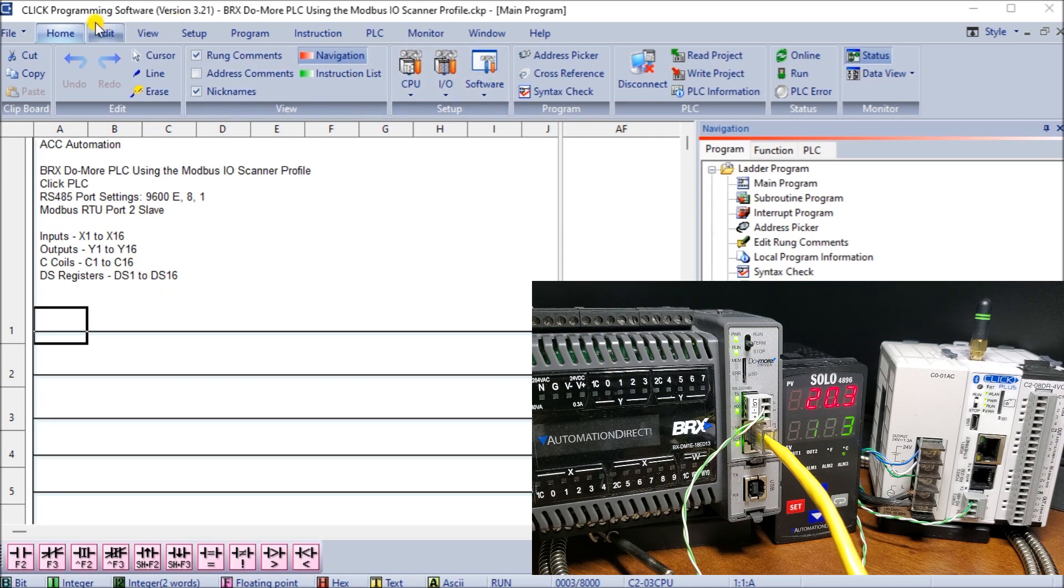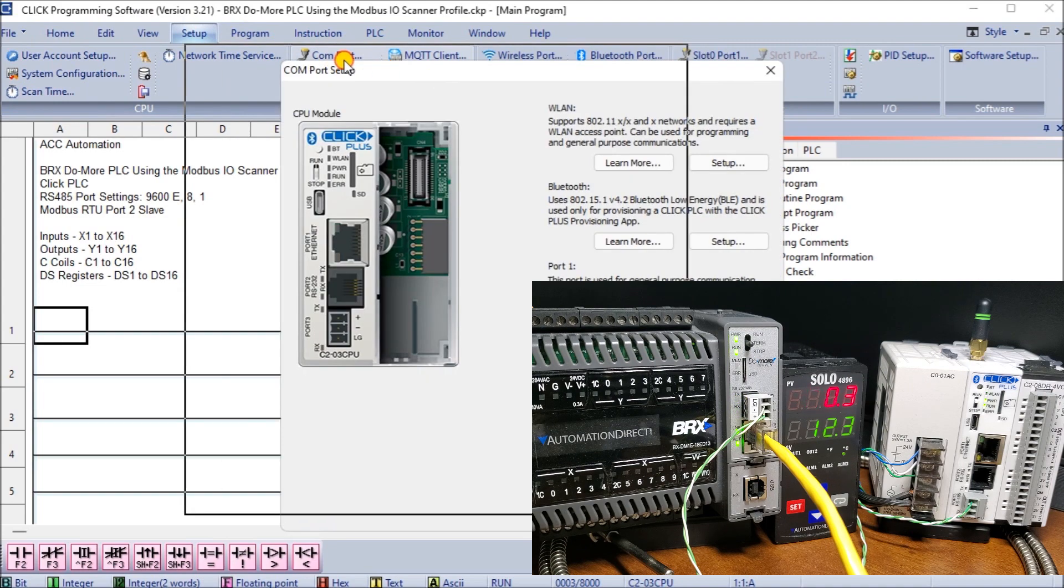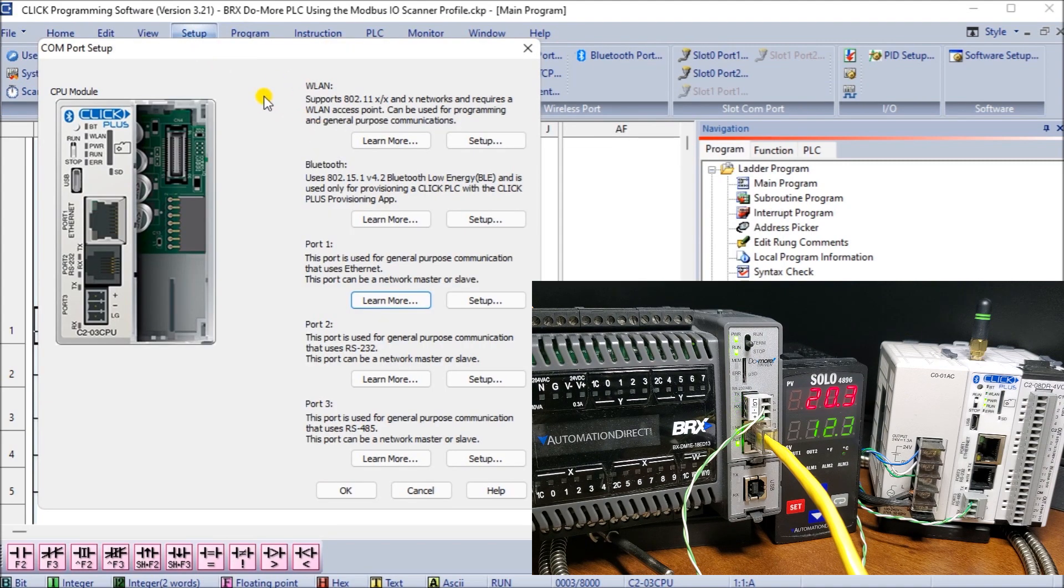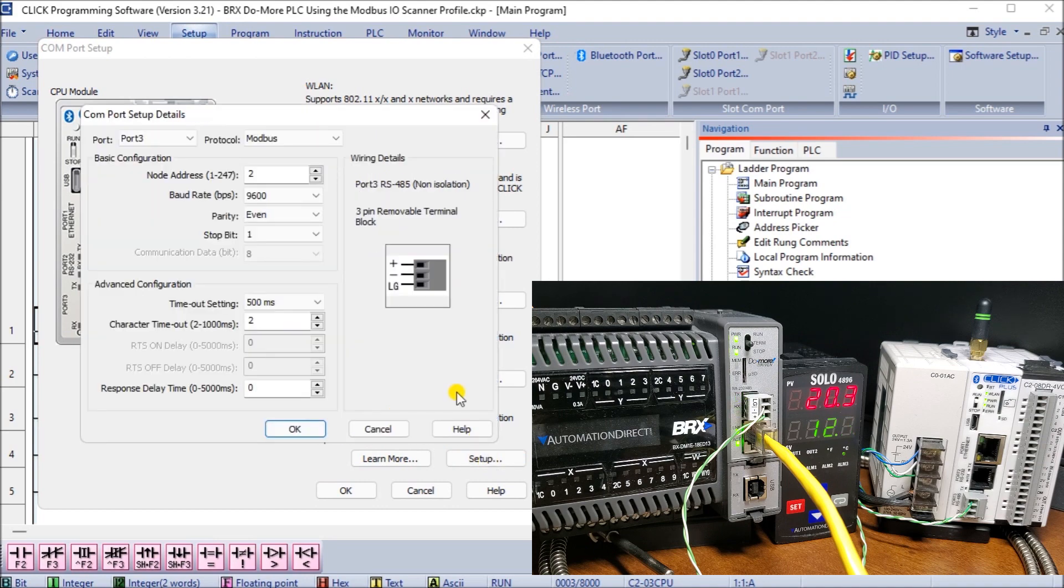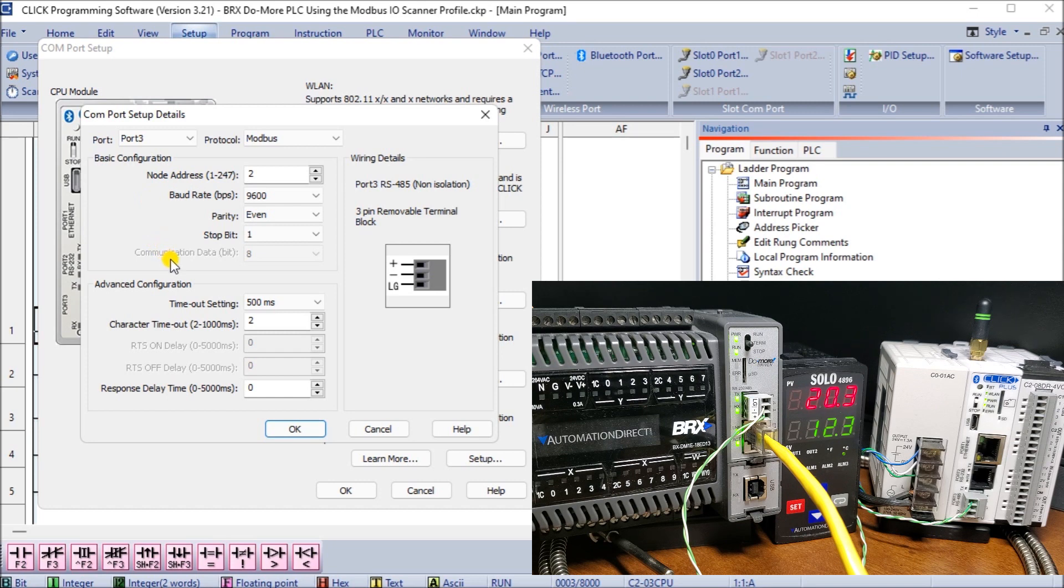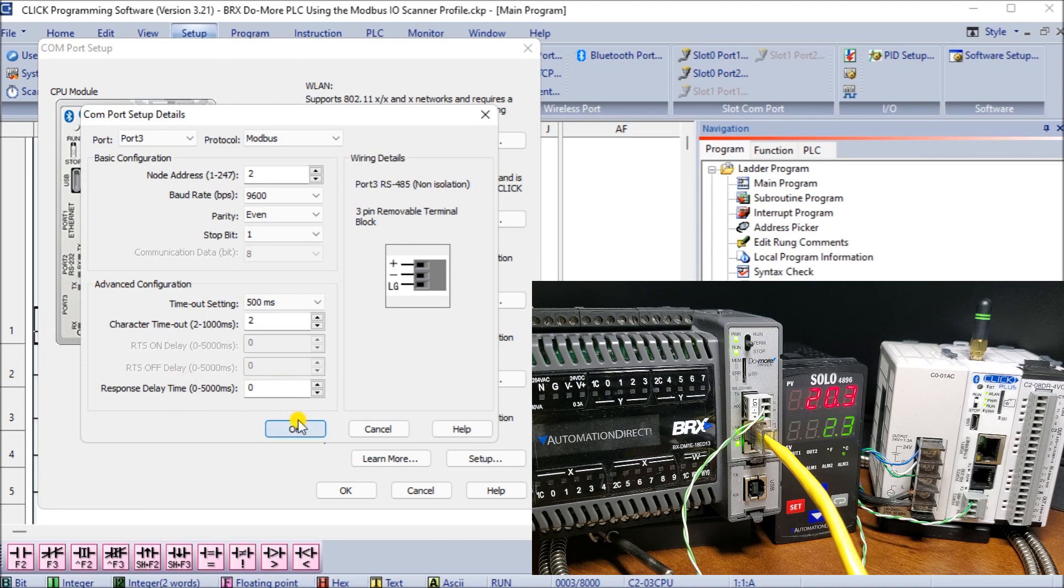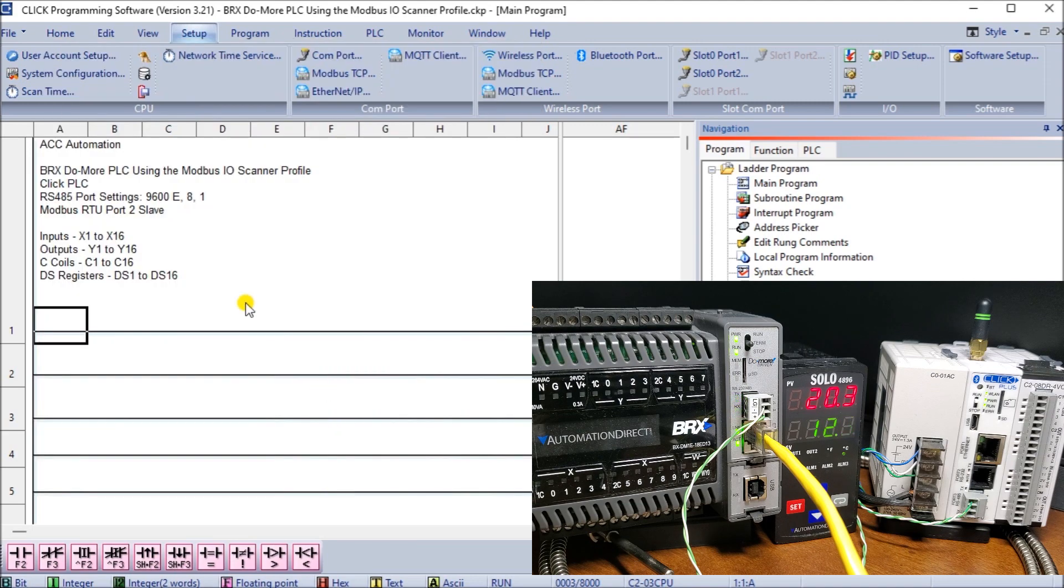So here is my Click programming software and if I go into setup and then we'll go com port, we can see here are our com ports that we have listed and port number three is actually our RS-485. So we'll set up, click on setup you can see that it's set for modbus. Our node address is actually node address number two. Our baud rate matches our previous setting which is 9600. The parity is even, stop bits are one and the data bits is eight. We will leave the default timeout settings and the character timeout set codes and everything in response to delay time. So hit okay so that's all set up. And basically we will not have a program within this controller.